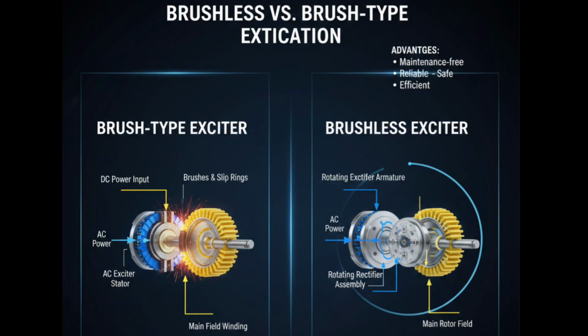Brushless vs brush-type excitation. On this slide, we compare the traditional brush-type excitation system and the modern brushless system. Notice the side-by-side 3D graphics, one showing brushes and slip rings in the conventional system, and the other showing a rotating rectifier and AC exciter in the brushless design.